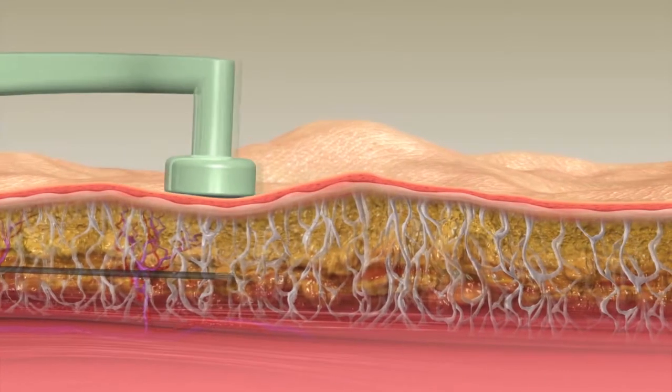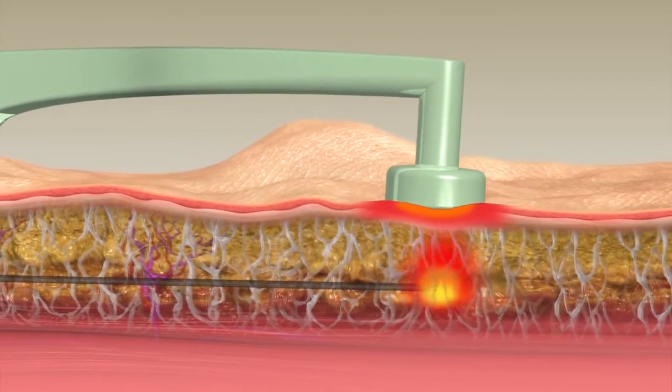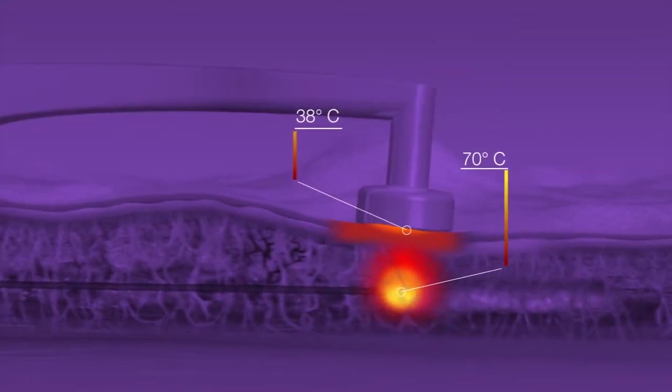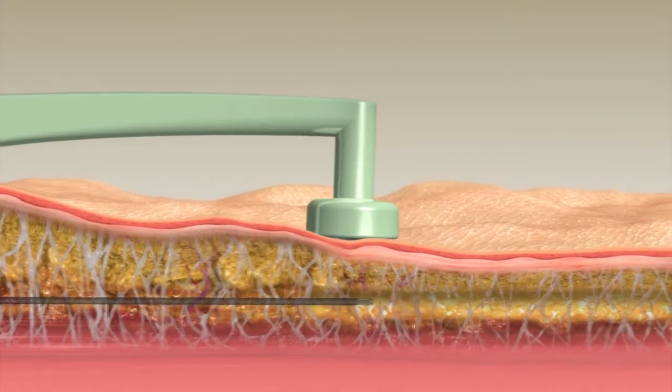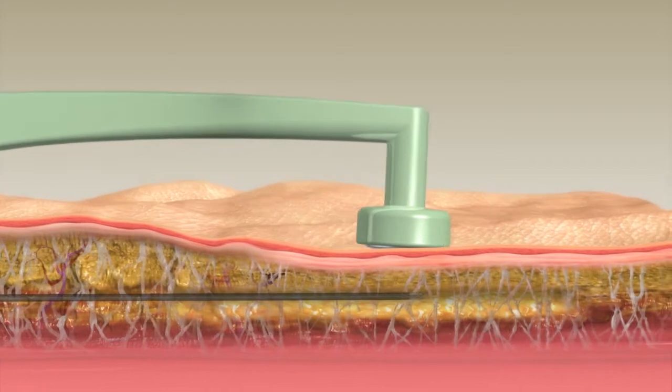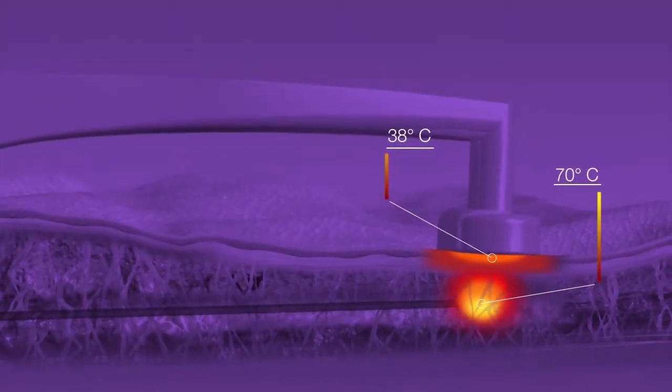The BodyTite contouring procedure uses radiofrequency energy for internal fat lipolysis and external collagen contraction. RF energy flows from the internal cannula toward the external electrode placed on the skin's surface. RF power is regulated based upon online measurements of skin temperature and tissue impedance.